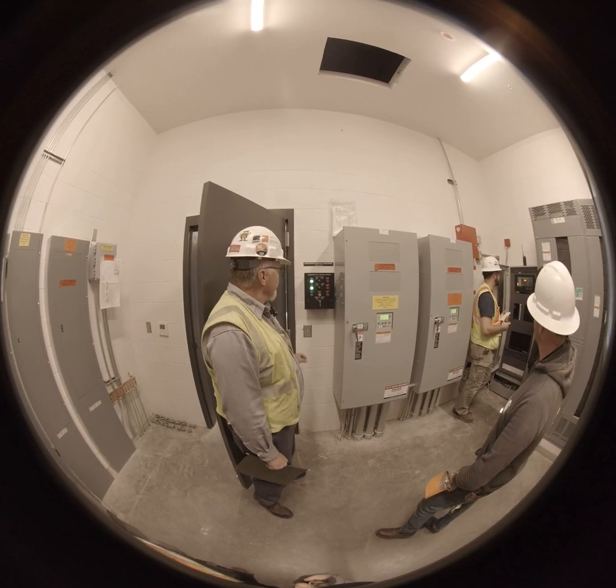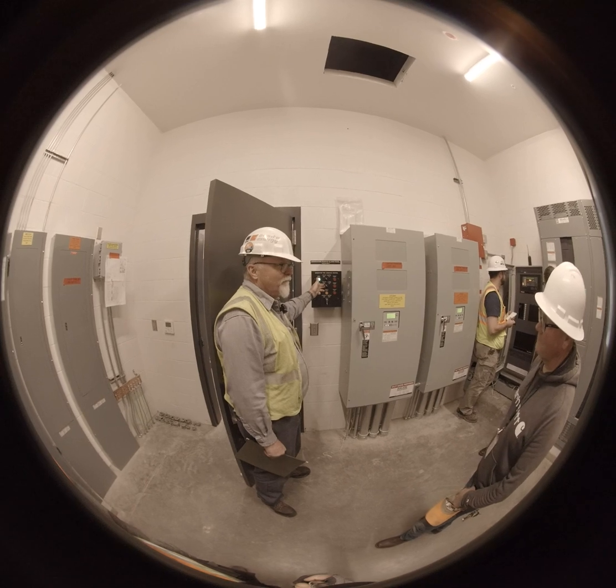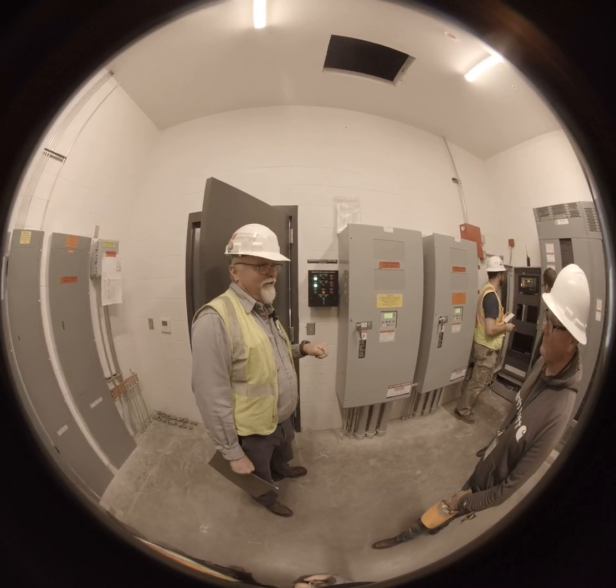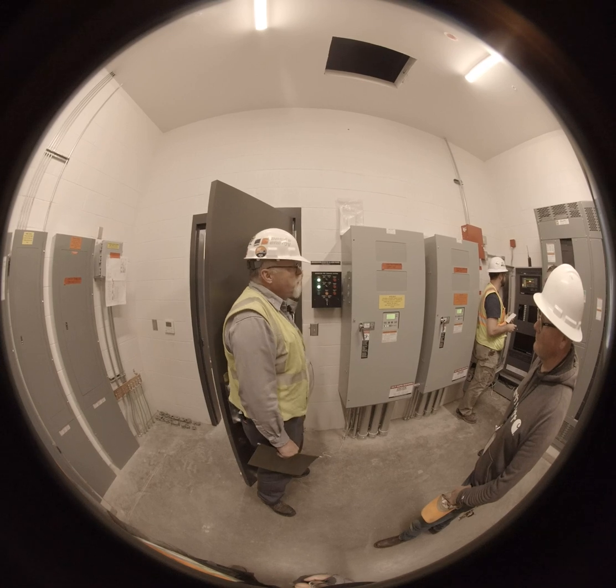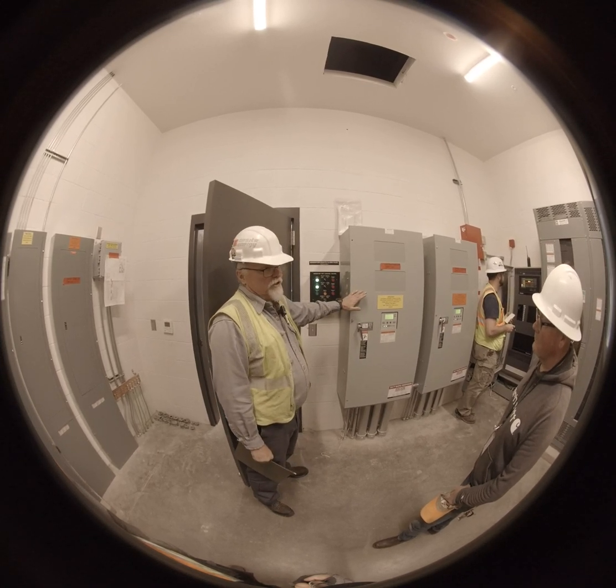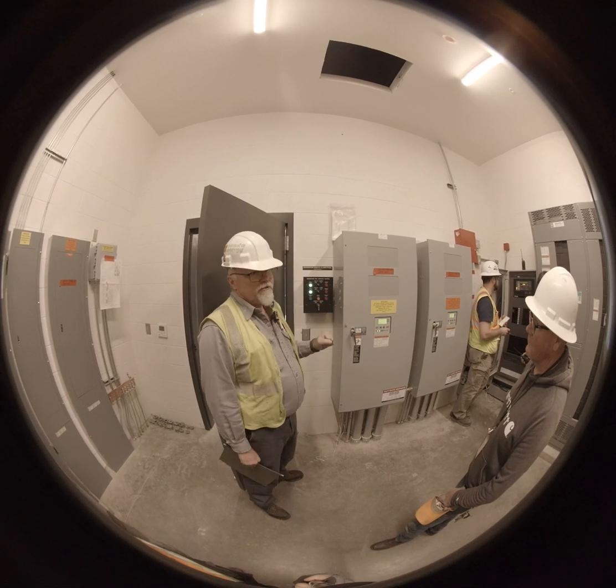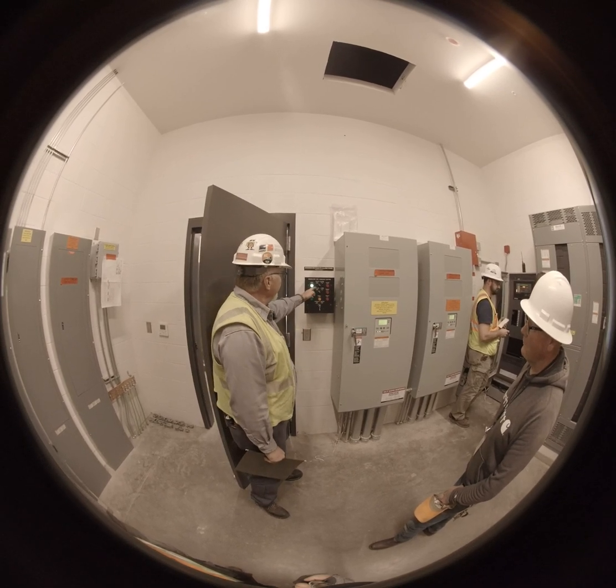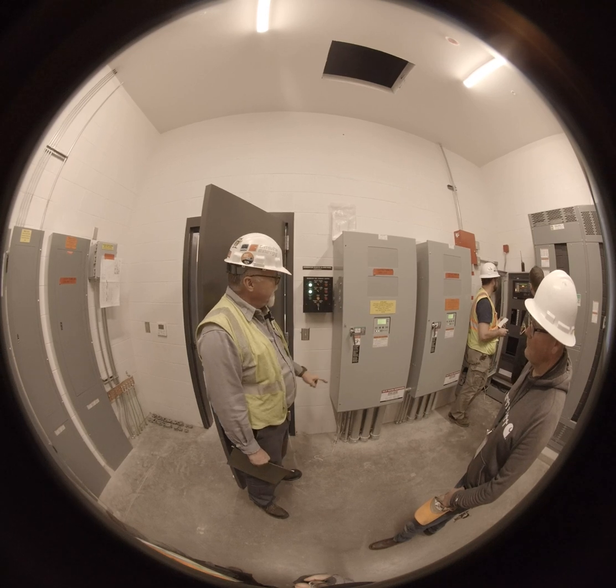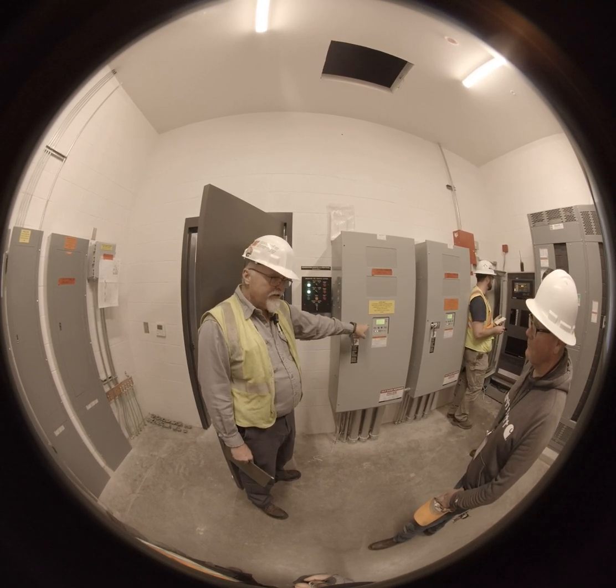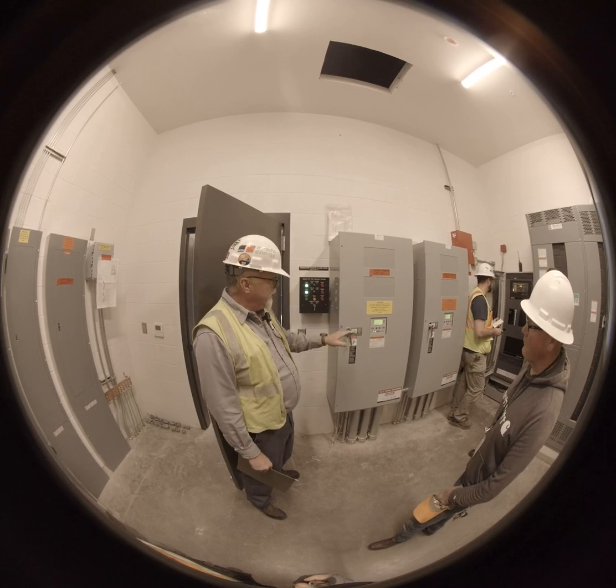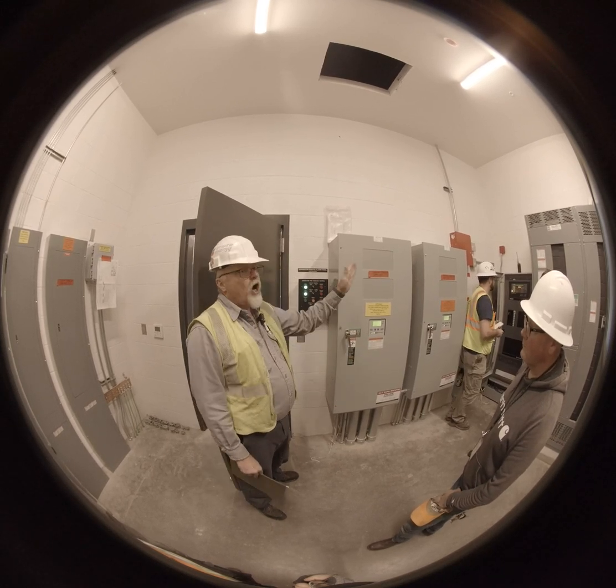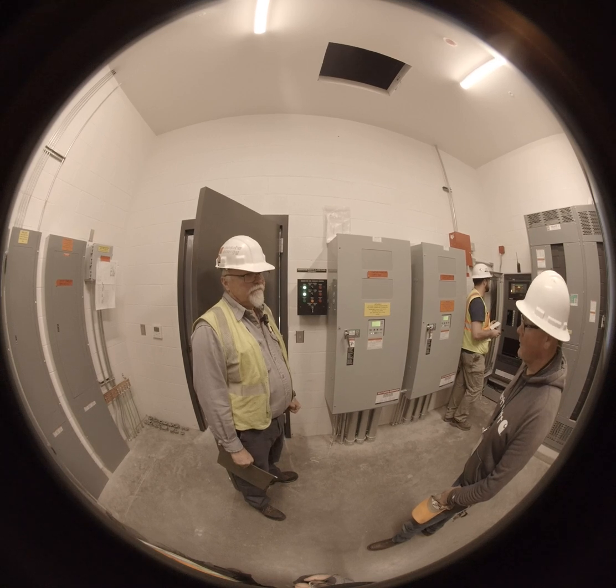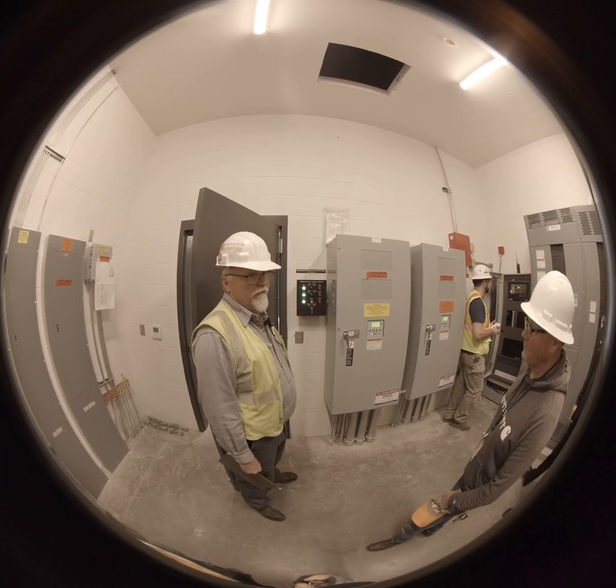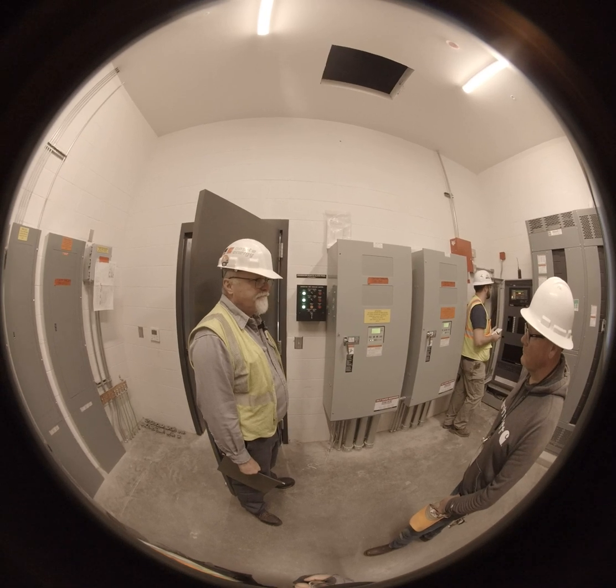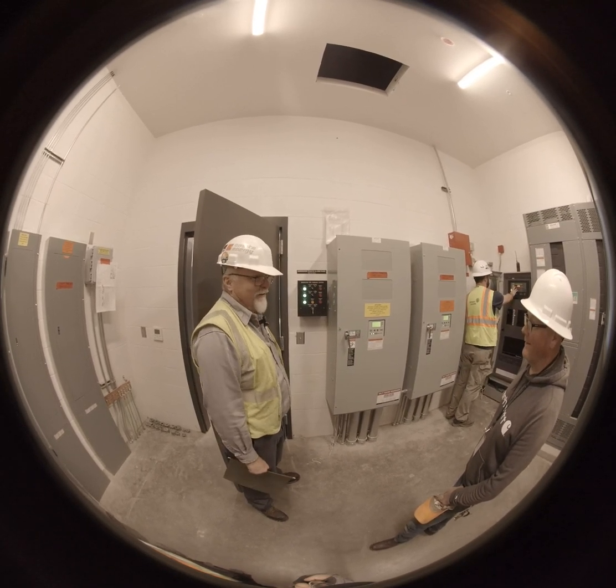Okay. Now, these two guys up here will probably upset these two guys over here. What these are is you can basically tell this transfer switch to go to the secondary source, to the generator source. So if I flip this over to force to gen, this transfer switch is going to come up with accessory 17 on the display, and it's going to start the generator set, and it's going to transition onto the generator. And it will stay there until you turn this back. And I'm not sure where their testing is, so I don't want to mess with them at the moment.